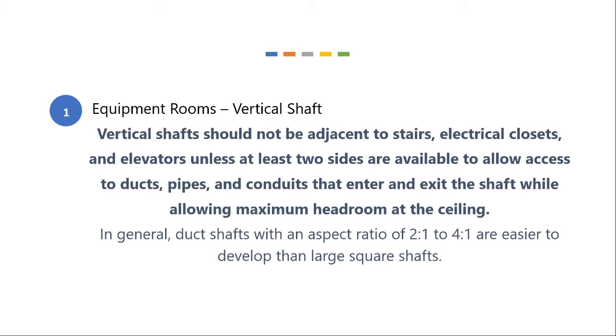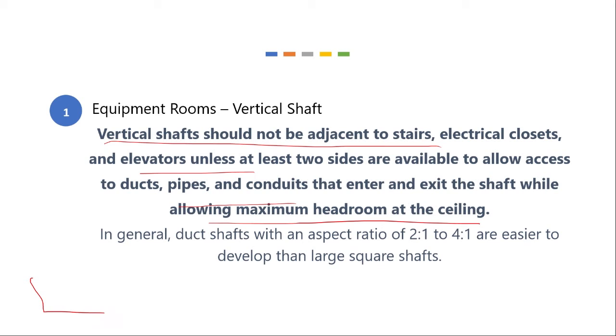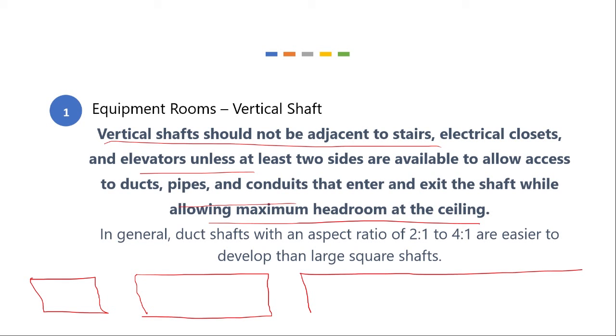So it's important to consider not to put a vertical shaft next to a staircase or an elevator unless 2 sides are available so that you can access ducts, pipes, and conduits. And you need to allow maximum headroom in the ceiling. It's easier to build a shaft that is 2-to-1 or 4-to-1 rather than a square. We'll learn more about this later, but in general, a shaft that looks like this, and this is supposed to be a square, is a lot more difficult than a shaft that's like this, 2-to-1, or even a shaft that's like this, 4-to-1. This is much easier to build. This is a lot more difficult to build.